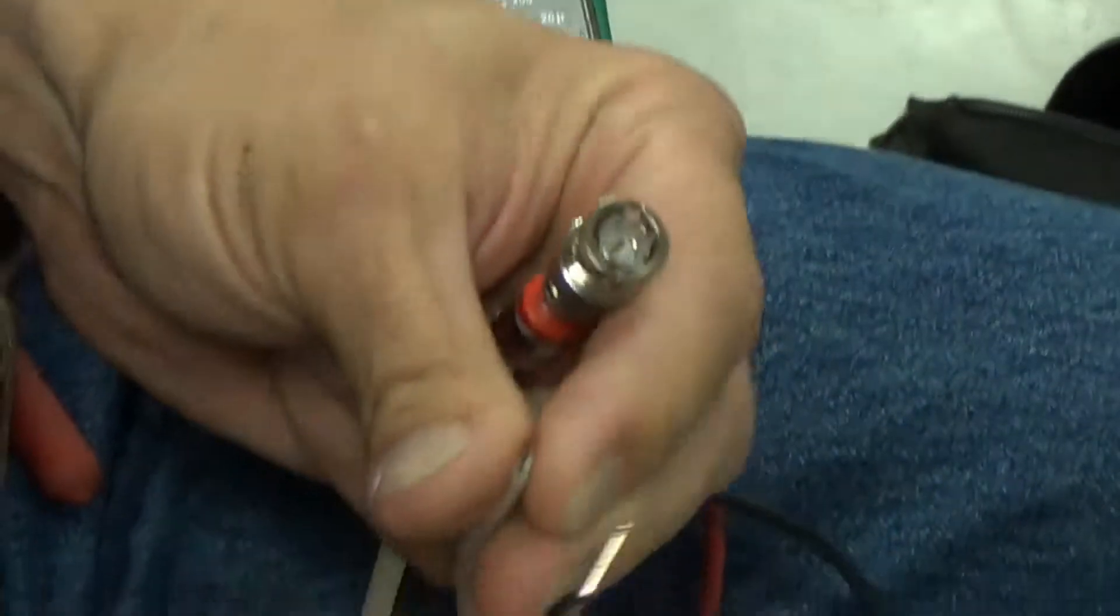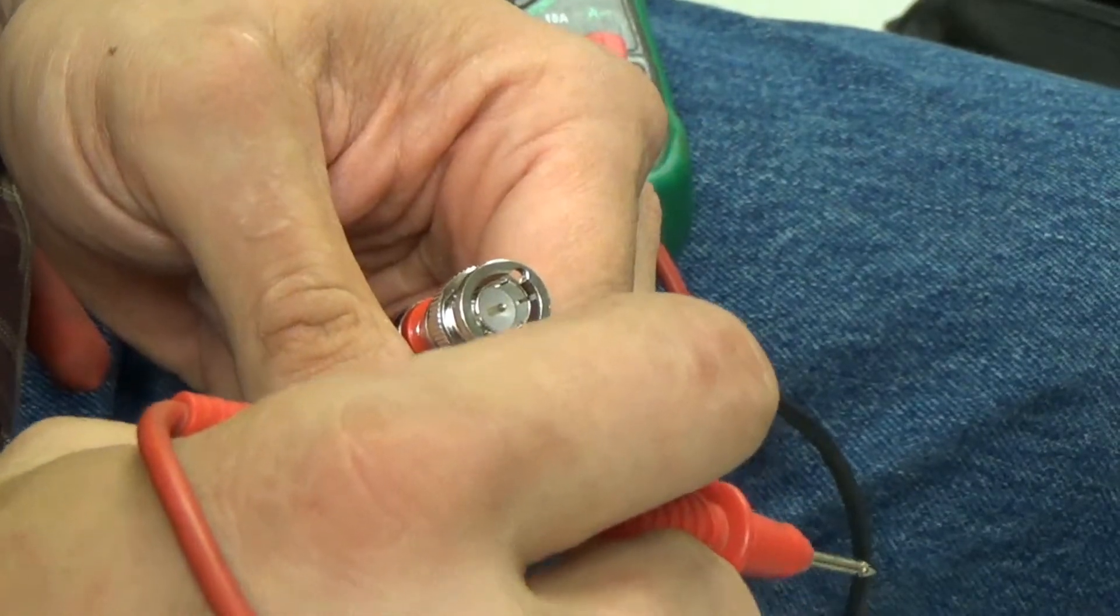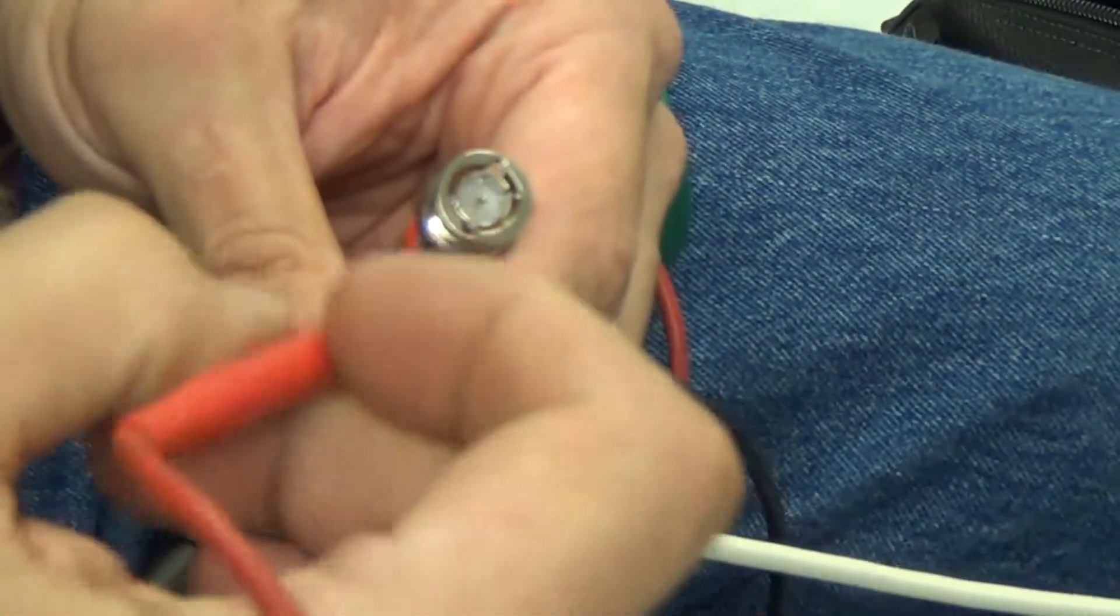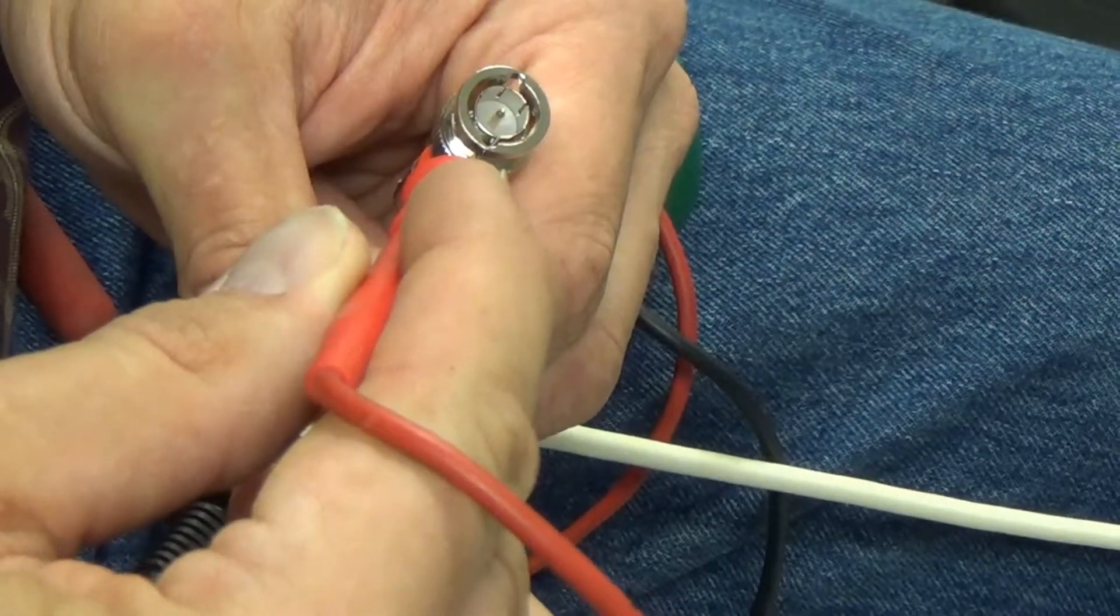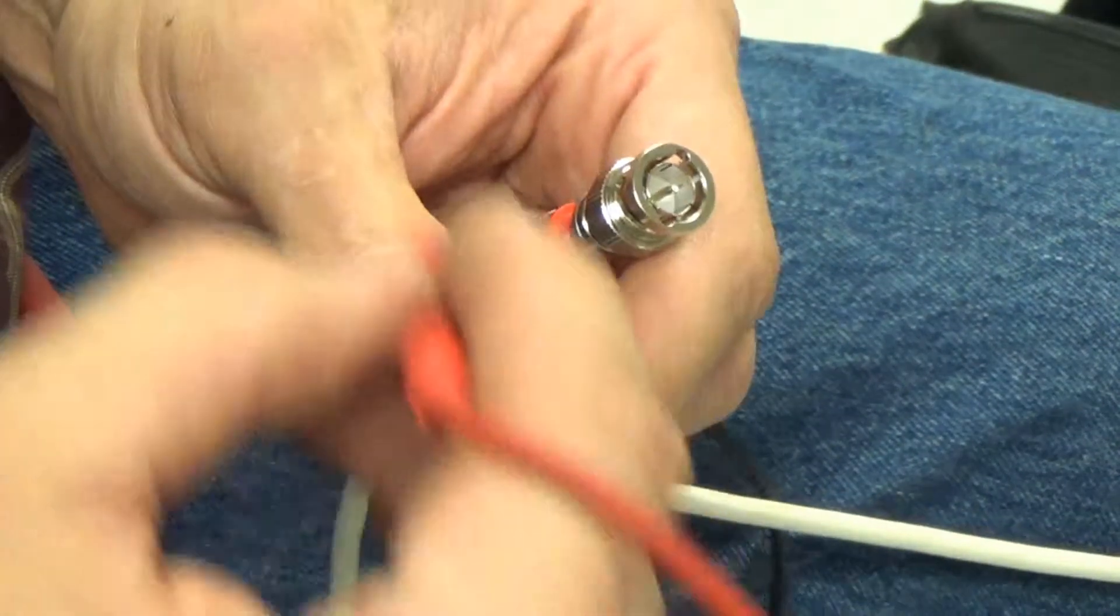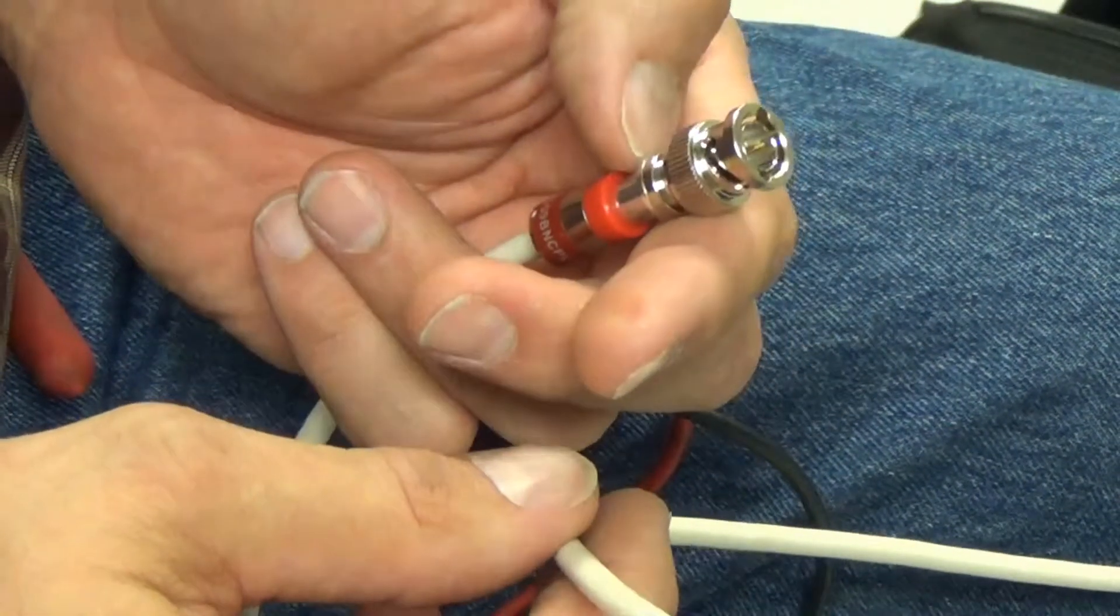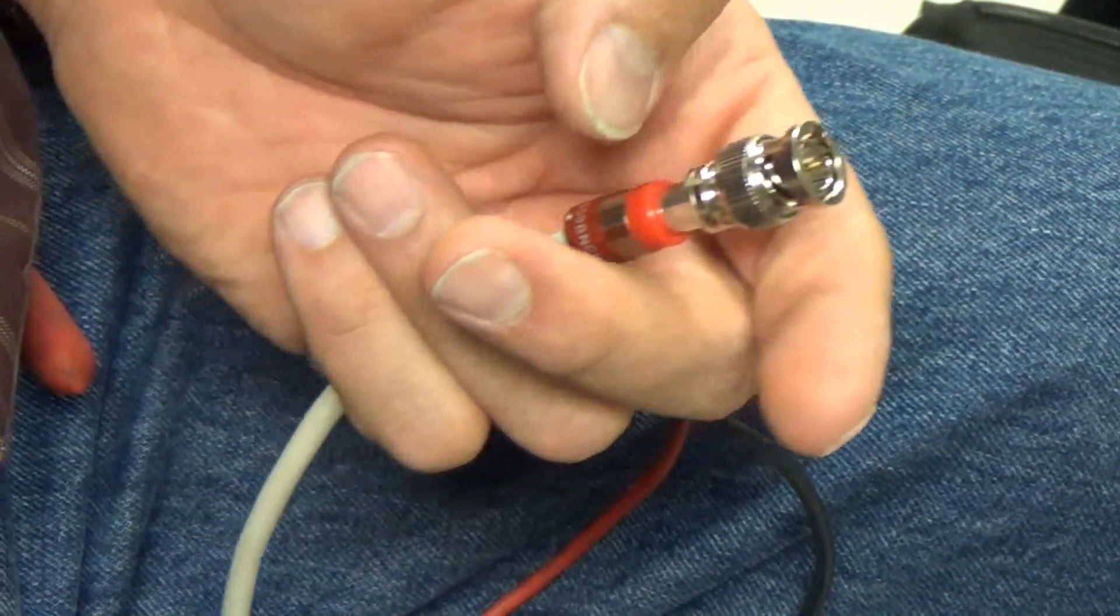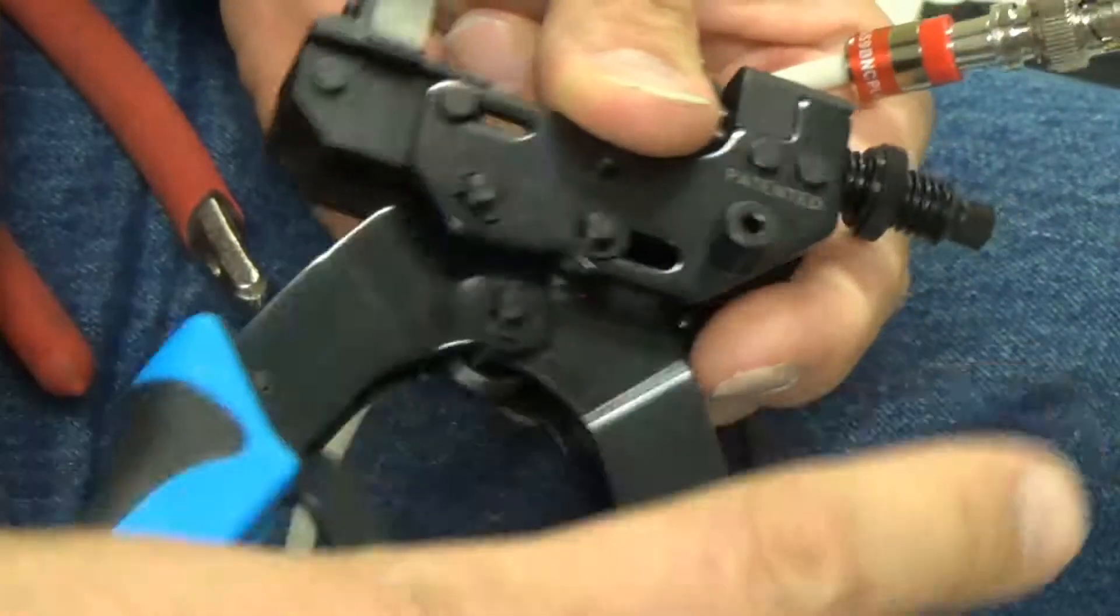So I should show nothing on ground. And if you want to be just a little bit more, if you want to be a little bit more anally retentive about it, you can actually stick your ground down inside like that, down in your ground, and touch ground over here. And that shows me that this connector is grounded good. The ground inside of my jacket here is well done. And I will, every time, actually not usually, every time I make one of these connectors, just because they're kind of long and a little funky, I always like to make those checks before I do my crimp. Once you've done your crimp, that's it, you're done. So you want to make sure that everything's got proper continuity before you do your crimp.